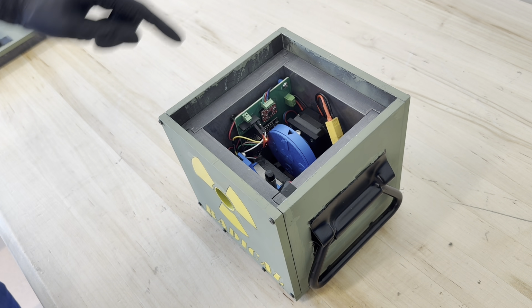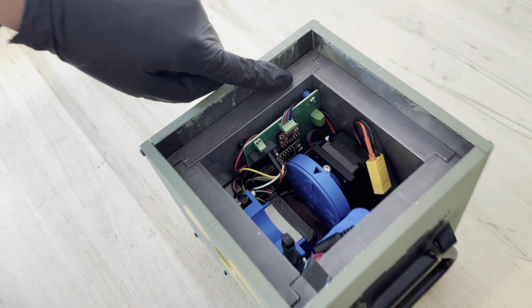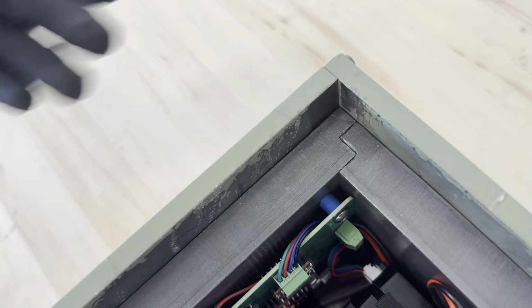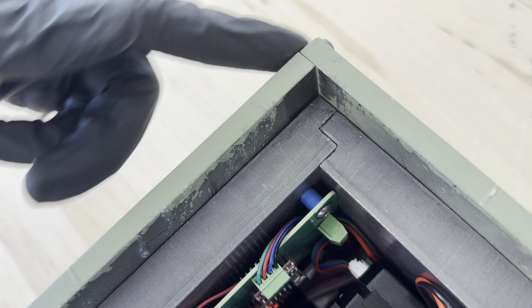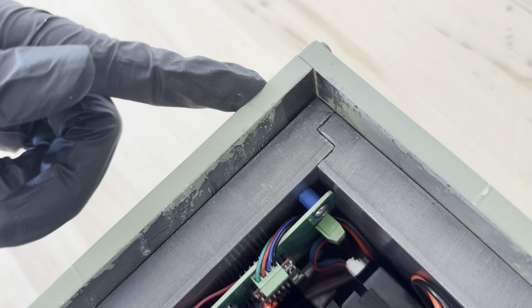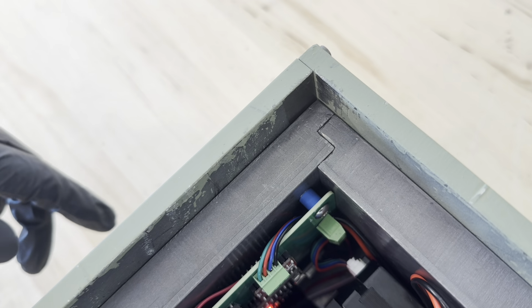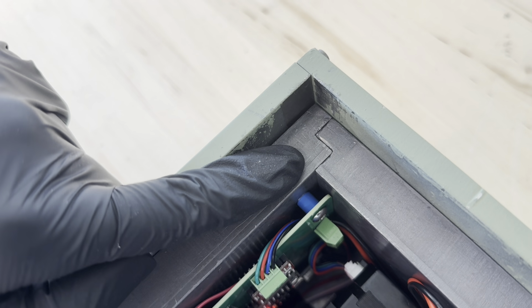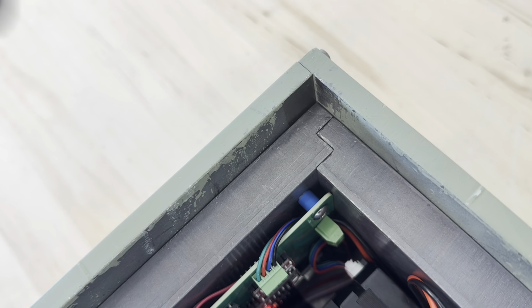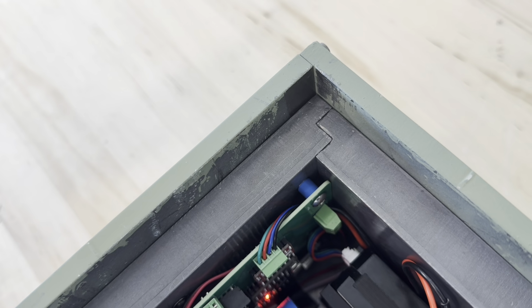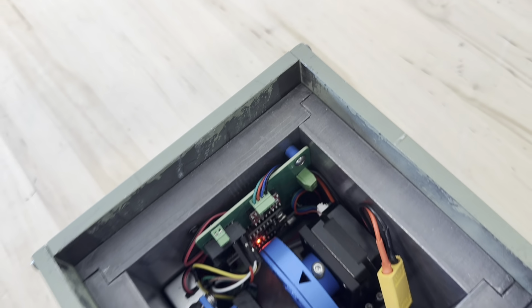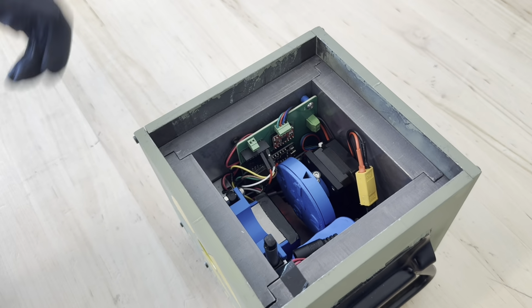You will see that the lead panels are joined in an interesting way. Instead of having simple butt joints like on the steel plates, we went for a double rabbet joint on the lead layer. This was done to prevent any straight line seams on this layer, which can cause potential radiation leakages.